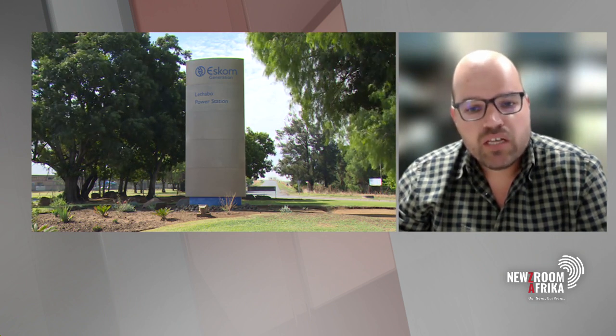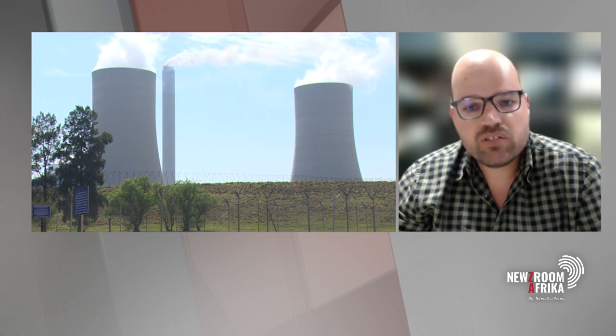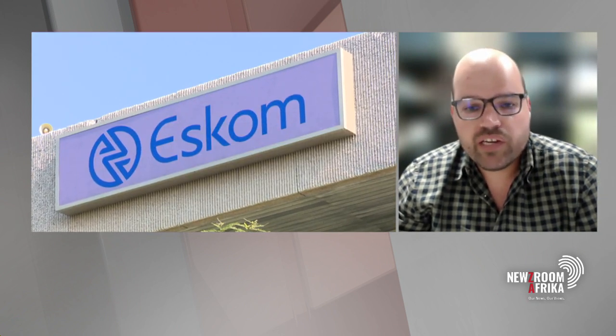Well Stephen, the technical term for this is called cold load pickup. This is a phenomenon that occurs during an extended period without power, and when the power comes on, all loads in that vicinity switch on immediately and simultaneously. So it could be geysers or air conditioning, where the temperature has dropped, and to compensate for the period these devices were switched off, they switch on simultaneously. This causes excessive loading for a short period within that mini-sub or transformer within the substation. So during load shedding, where this happens multiple times, the combined effect of this intense load on the substation causes failure of that substation.